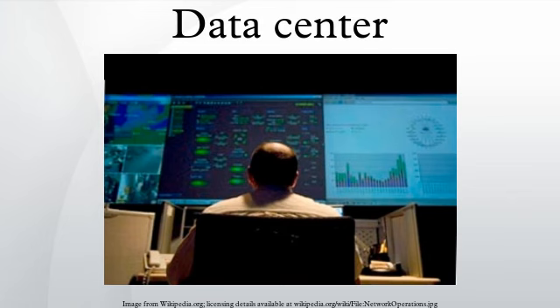Whilst no downtime is ideal, the tier system allows for unavailability of services as listed below over a period of 1 year. Tier 1 status would allow 1,729.224 minutes, Tier 2 status would allow 1,361.304 minutes, Tier 3 status would allow 94.608 minutes, Tier 4 status would allow 26.28 minutes. The Uptime Institute also classifies the tiers in different categories: design documents, constructed facility, operational sustainability, design considerations.